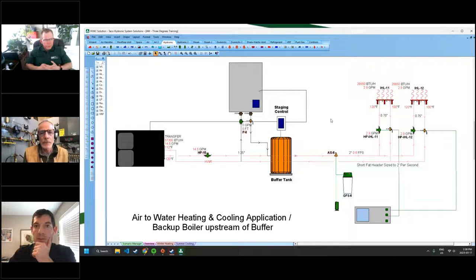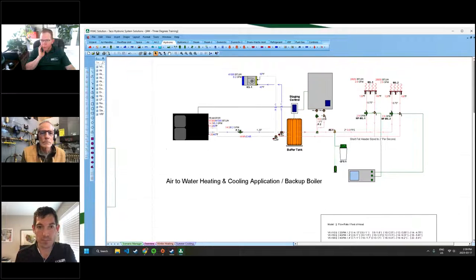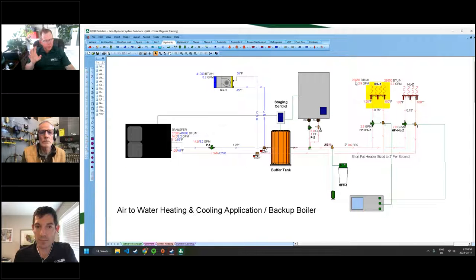If you have one zone, so if you put in an air to water heat pump, it would be very different than a house where you've got a towel rack and you might have a small bedroom. You have seven different zones in the house that the buffer tank would be needed to sip off of that little battery. You could pipe it completely different if you're just trying to do one run cycle, but you only have one flow condition on the system side. It's either the shop is on or the shop is off. There's one pump going out there, and that determines how you navigate all these different buffer tank piping diagrams as well. Nice part about both are right, as Bob and Max have both alluded to. What I like about this is I know exactly what my system is doing.